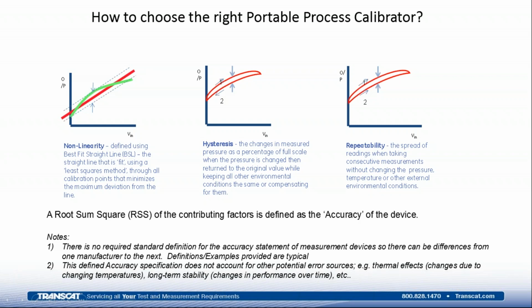So a couple notes on this. There is no required standard definition for the accuracy statement of measurement devices, so there can be differences from one manufacturer to the next. These definitions and examples that I've provided here are typical. So it's important to look at and understand the definitions of accuracy or performance for the device being calibrated. Accuracy, as we've defined it here, does not account for other potential error sources, such as thermal effects, which are changes due to changing temperatures, or long-term stability, that's changes in output or changes in performance over time. There are other potential error sources that could contribute to the uncertainty of the device, and I'll move on to the definition of uncertainty on the next slide.